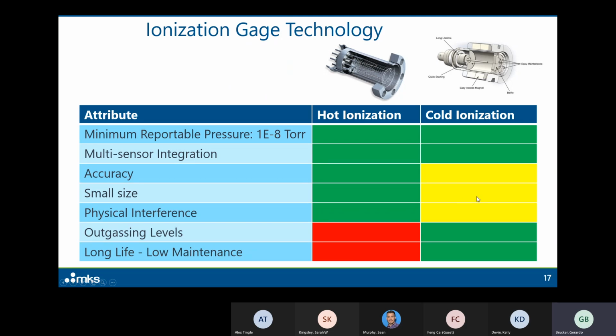We didn't know how small we could make the cold cathode gauge at that point. We also knew that hot cathode gauges have very little physical interference with the measurement, whereas cold cathode gauges, having magnets in them, could have more interference with the measurement, so we gave them a yellow. But then by the time we got to things like outgassing levels and lifetime, we knew that a cold cathode gauge was going to outperform a hot cathode gauge in these particular applications. So the question that, and this red is kind of a showstopper. Yellow means maybe we can do something about this, right?